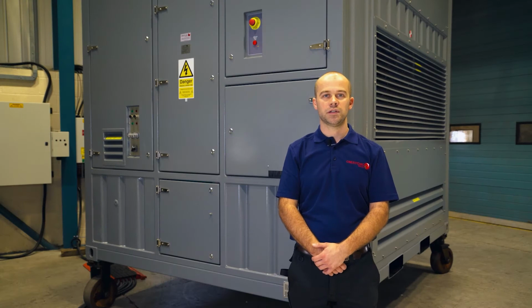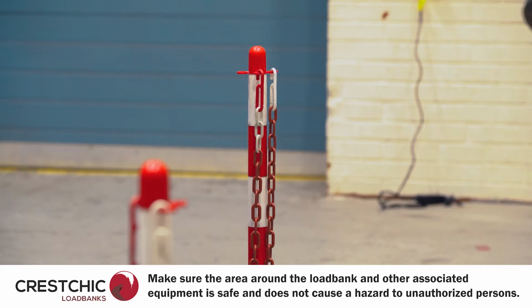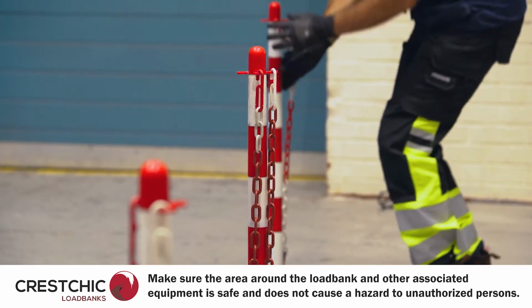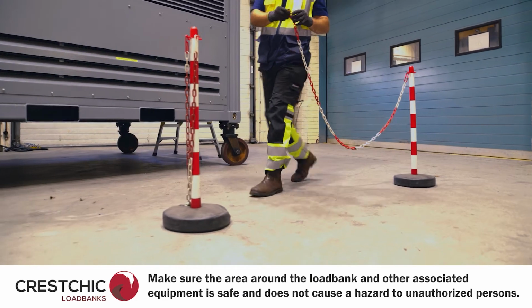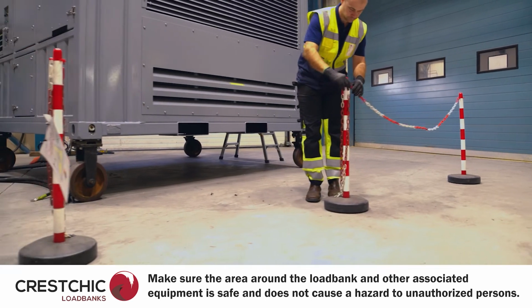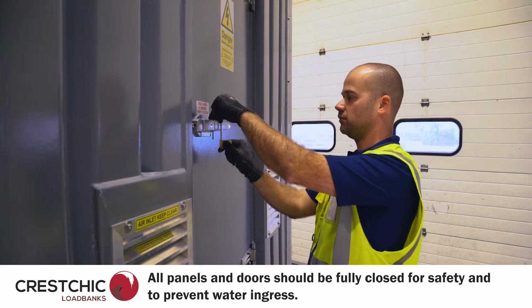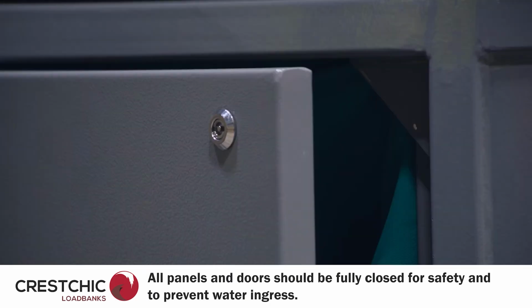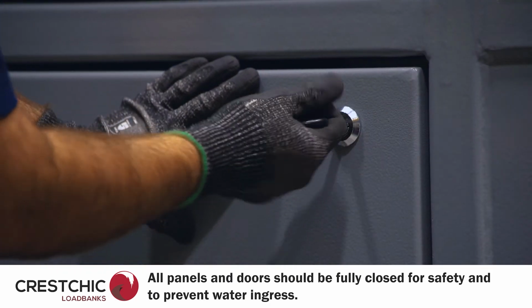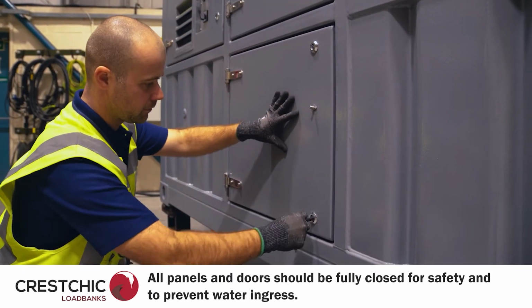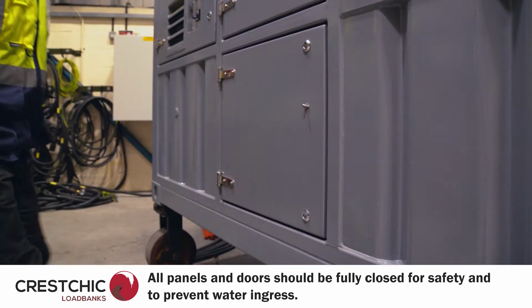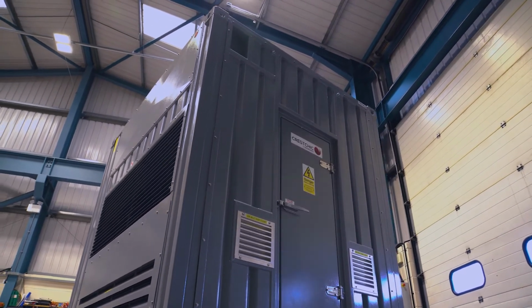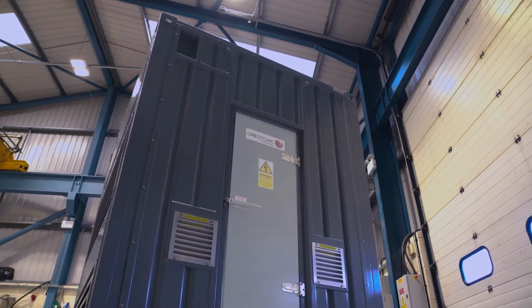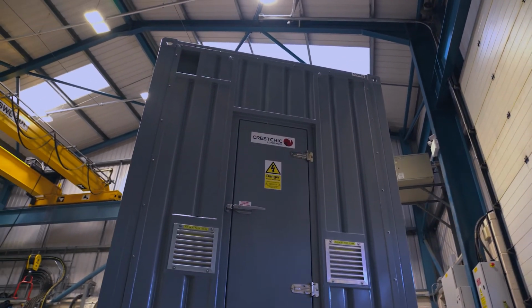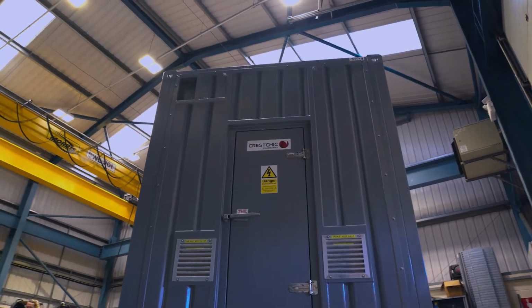Safety is most important during all work with the load bank, including the commissioning of it. We highly recommend erecting safety barriers around the load bank and other associated equipment to prevent unauthorised persons entering the area. During normal operation of the load bank, all panels and doors should be shut, making sure all catches on each panel are locked to create a good seal and prevent water ingress. During commissioning, some of these panels or doors will have to be opened to perform checks and connect cables. Care should be taken to prevent rain getting inside.